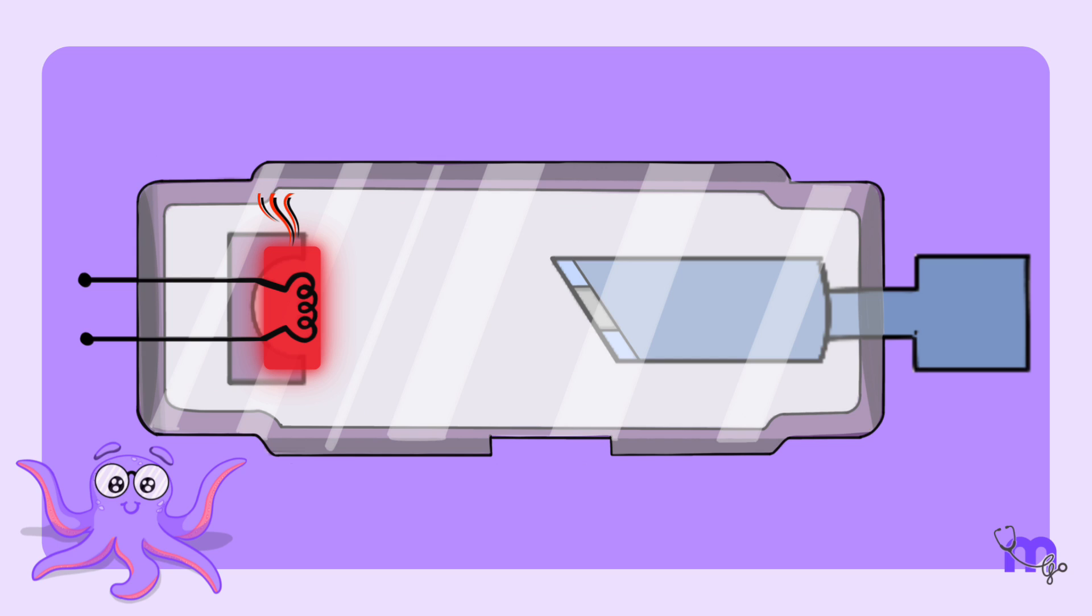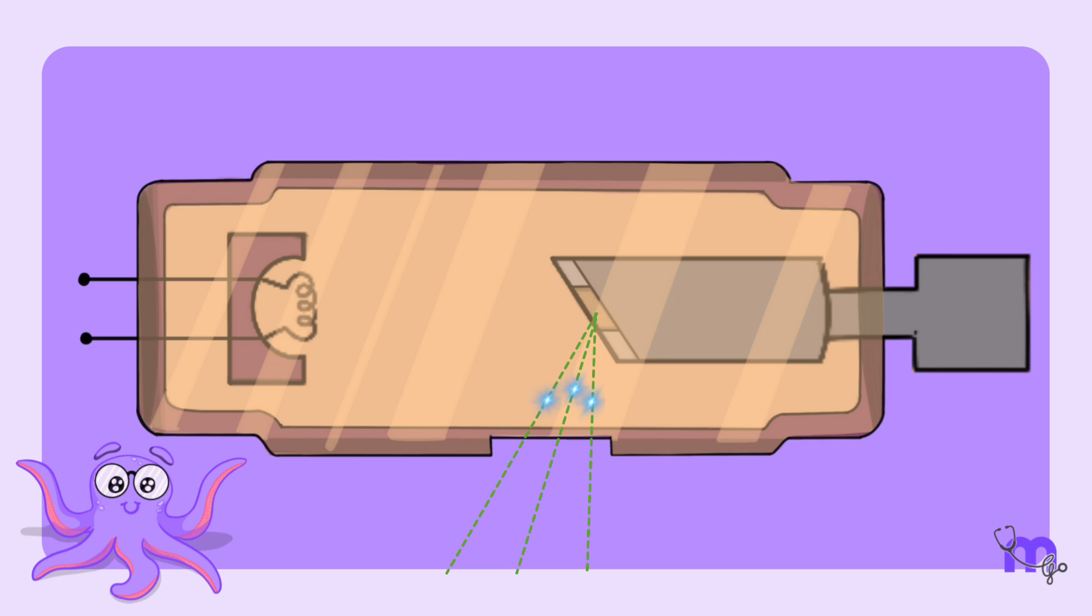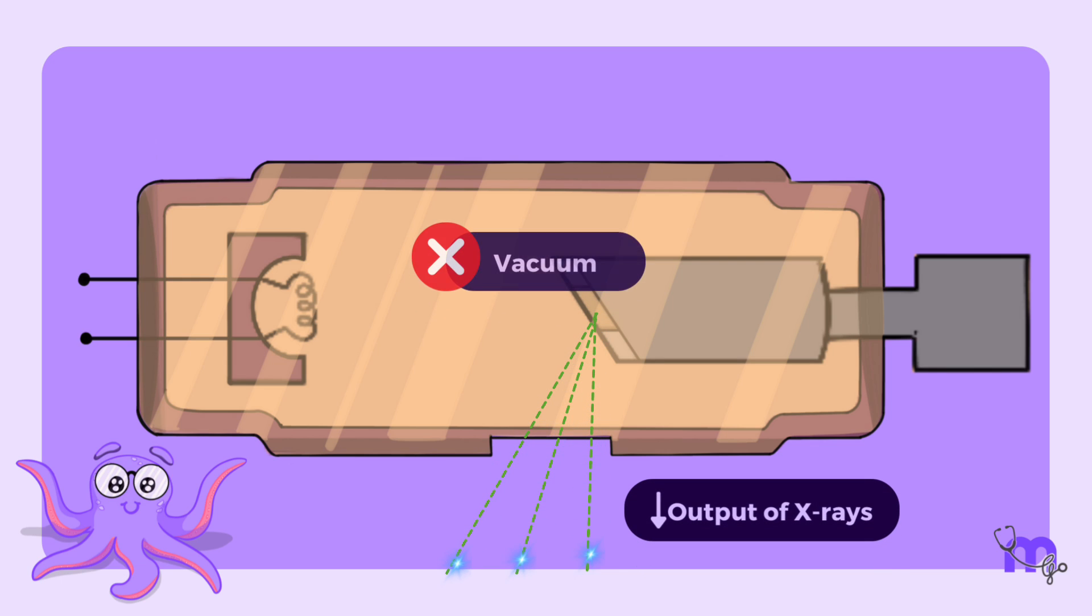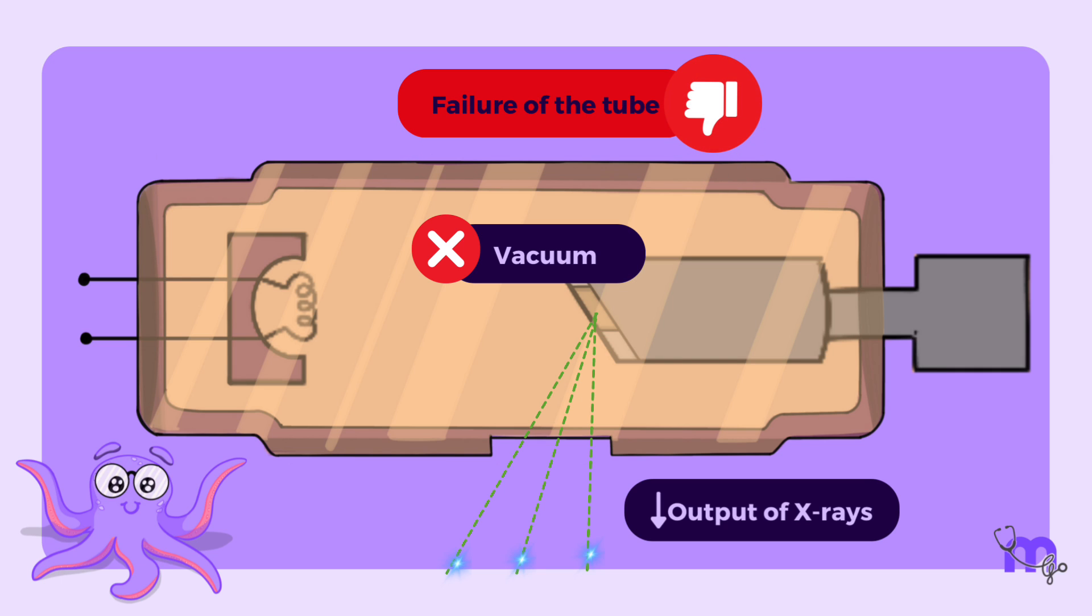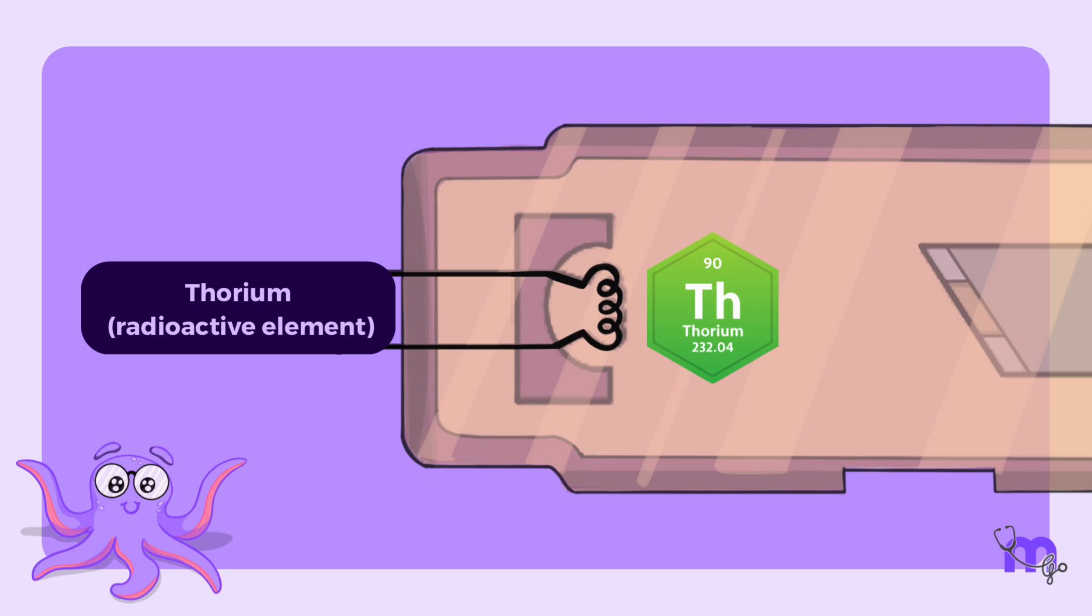Over time, the filament gets vaporized into gaseous form because of the heat and solidifies on the glass of the X-ray tube. This is called sun burning or sun tanning of the tube. This consequently leads to reduced output of the X-ray tube, destruction of the vacuum, and ultimately tube failure. To delay this process, thorium, a radioactive metallic element, is added to the filament material.